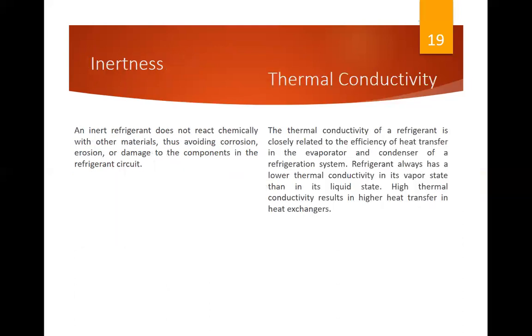Inertness. An inert refrigerant does not react chemically with other materials, thus avoiding corrosion, erosion, or damage to the components in the refrigerant circuit. Next, thermal conductivity of a refrigerant is closely related to the efficiency of heat transfer in the evaporator and condenser of a refrigeration system. Refrigerant always has a lower thermal conductivity in its vapor state than in its liquid state. Higher thermal conductivity results in higher heat transfer in the heat exchanger.